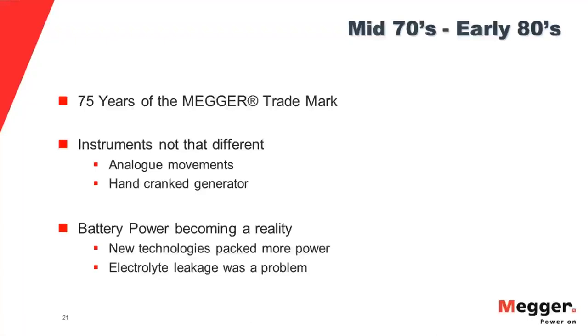Then eventually battery power started to come into use. But in the initial employment of battery power, not speaking of insulation testers in particular, but in electrical test equipment in general, there were a lot of problems with the old battery-powered units, and one of them is listed there, which would be electrolyte leakage, which would get into the workings of the unit and do a lot of damage. Other things were they didn't last very long, so sometimes to work a fairly intense shift, you had to take several sets of batteries, and if you forgot, then you were in trouble.